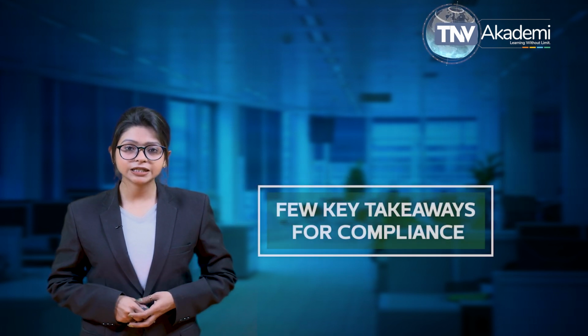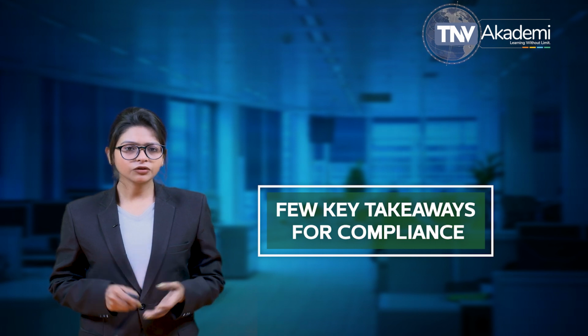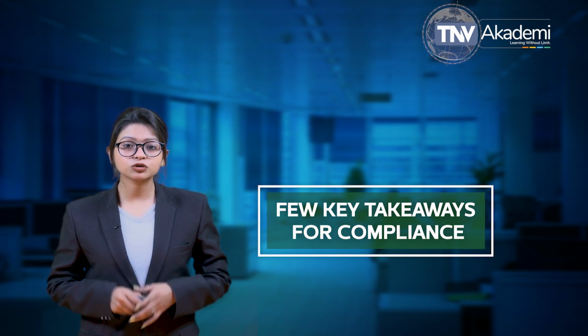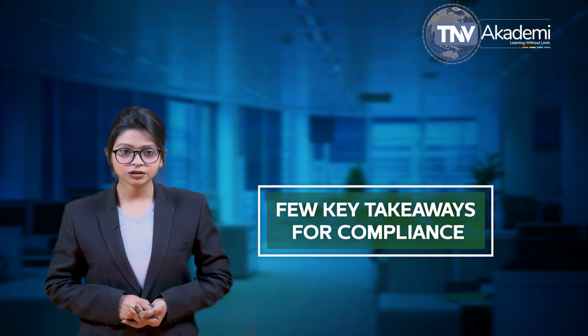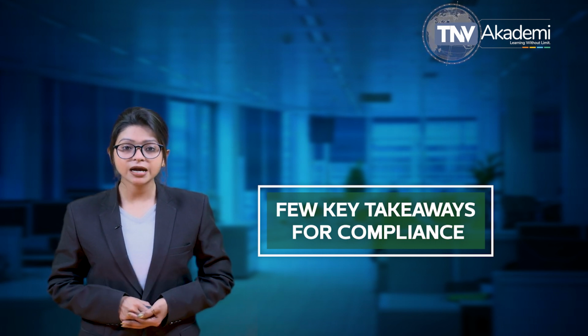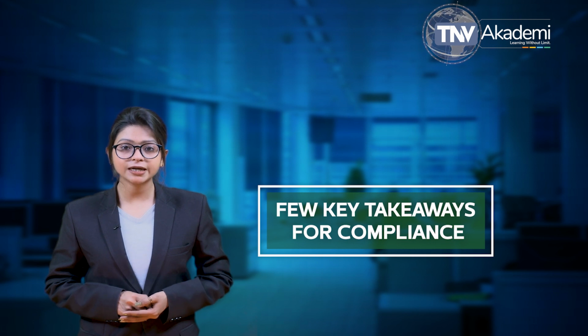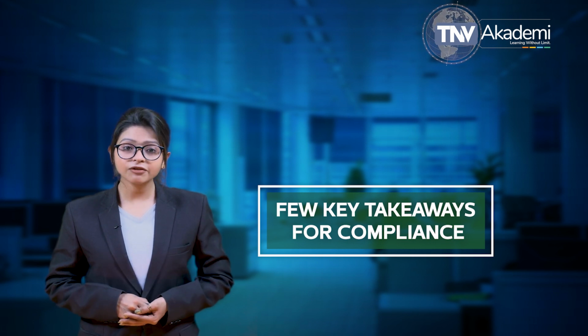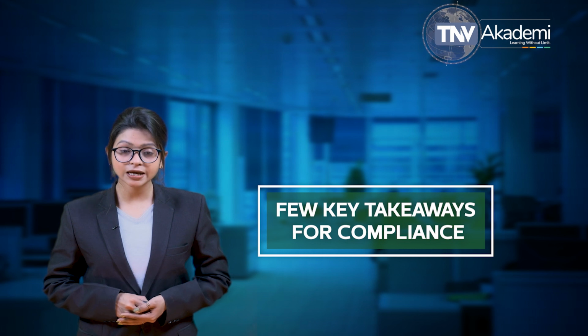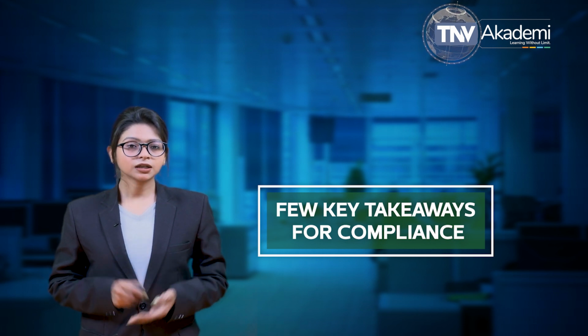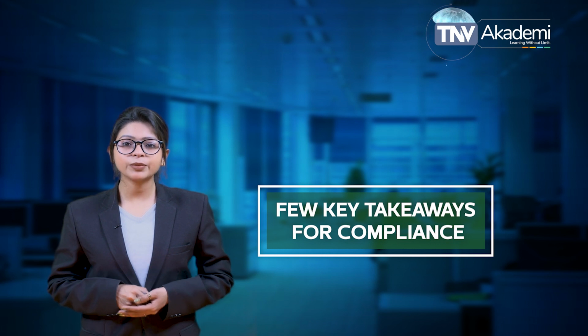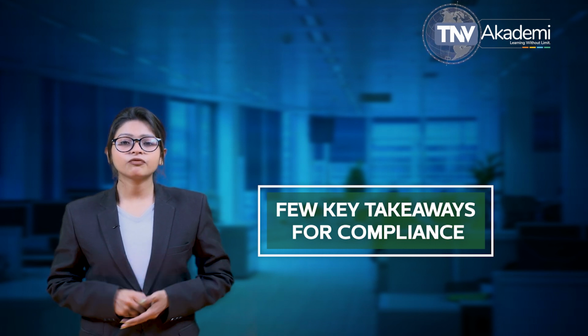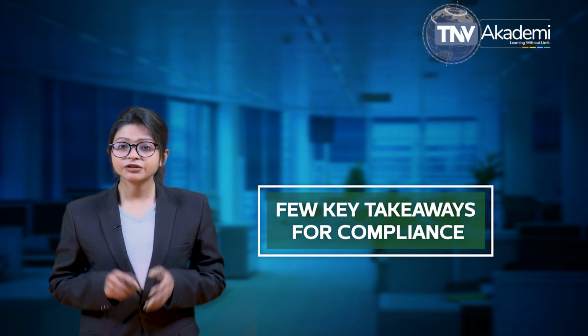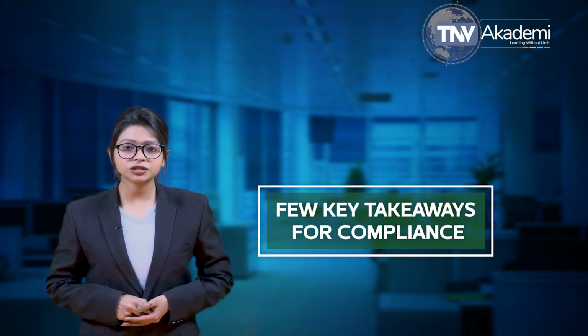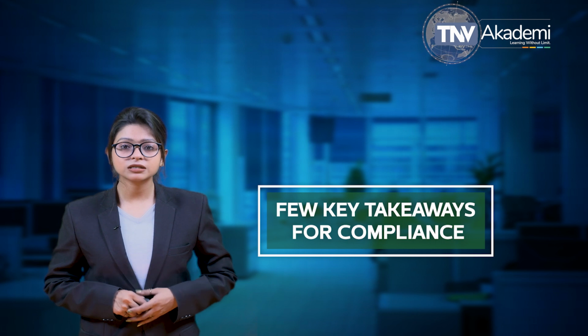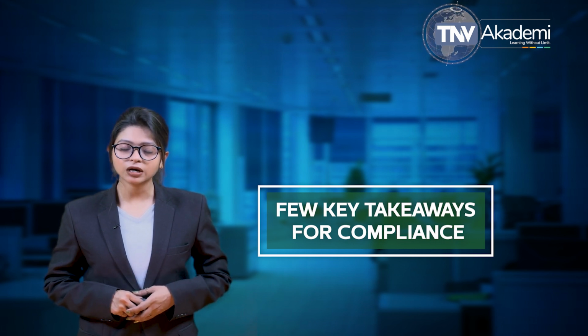Now, here are a few key takeaways for compliance. The first one is to use a risk-based approach to support the safety of your product. The second one is to use chemistry data and risk assessment to develop a biocompatibility test plan. This can often save unnecessary use of animals in testing and costly test articles. The third one is to outsource testing to an experienced laboratory partner that offers a full range of preclinical device testing services. This can be instrumental in accelerating the process and getting your device to market before others.